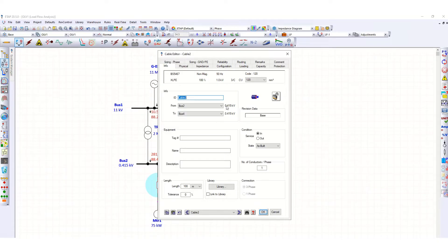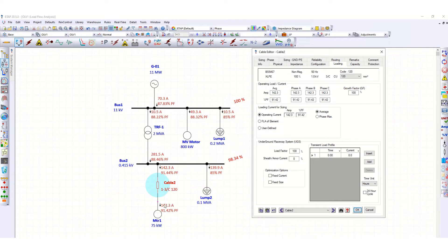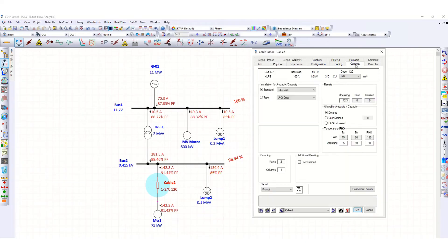Double-click here and go to the loading case. You can see 142.3 ampere current passing through this cable — this is the operating load current. Phase A, B, and C show the same values because this is balanced loading. The operating current is 142.3 ampere and power factor is 91.42 percent.